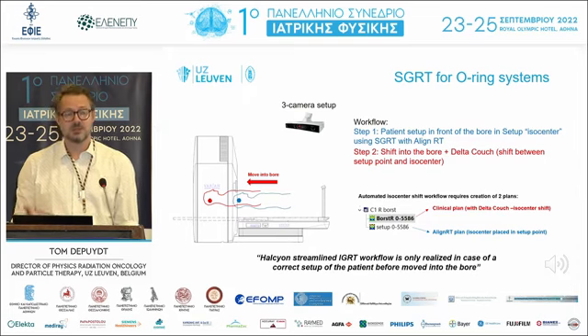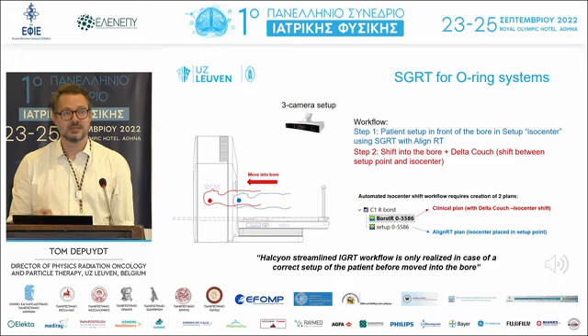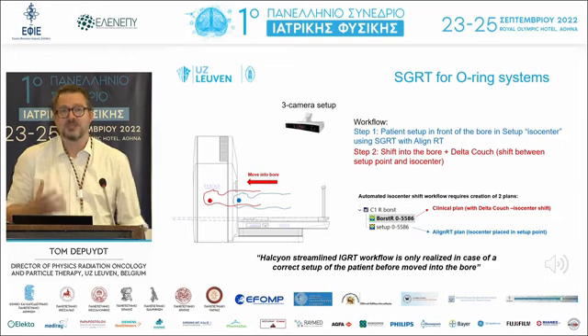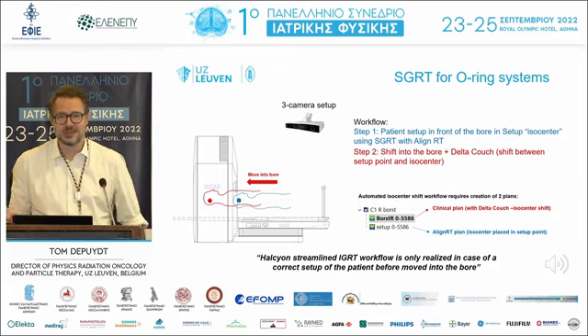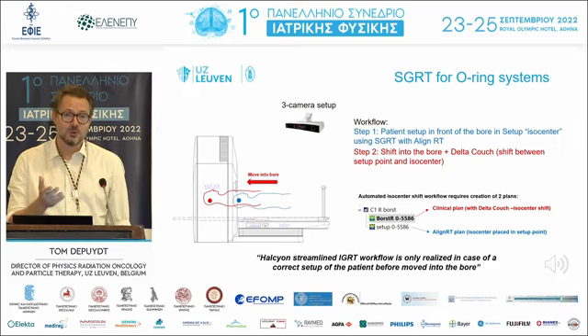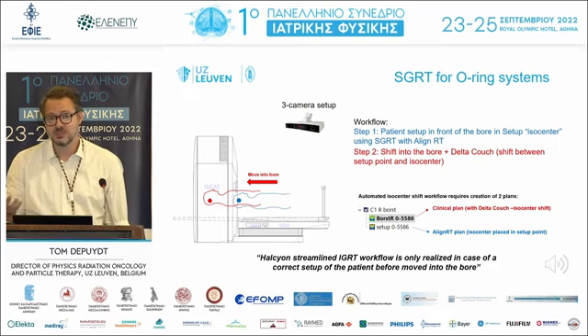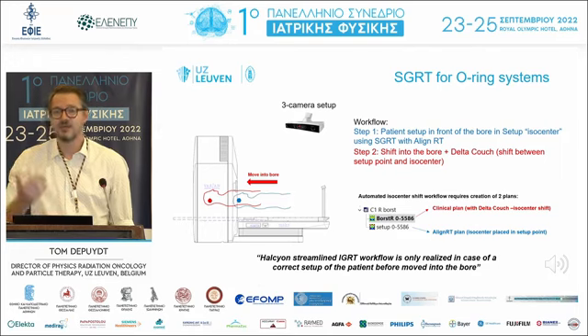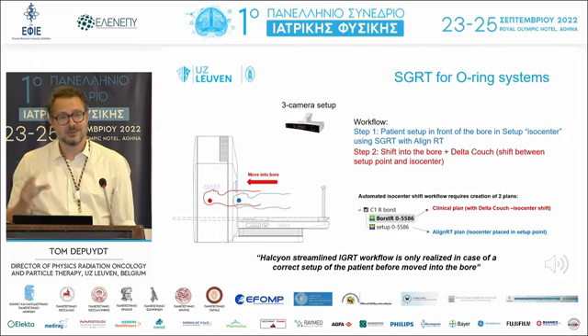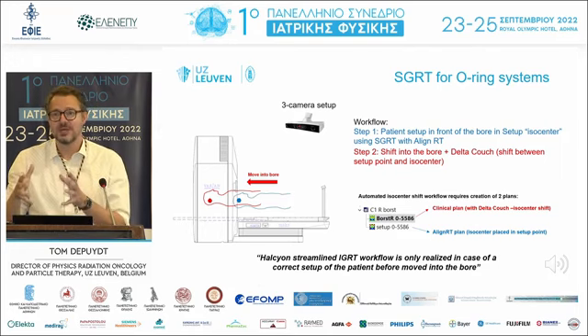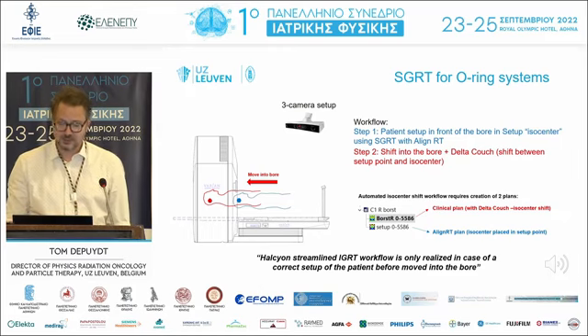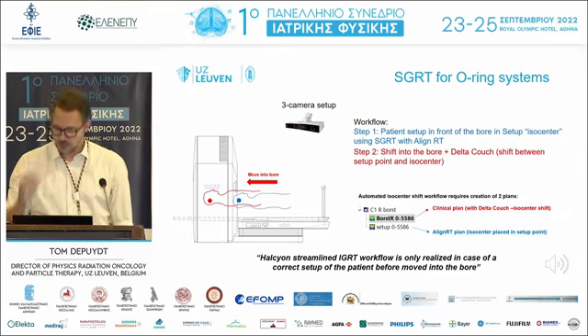So, streamlining Halcyon. Halcyon is a very fast device in the sense that it's really an efficient workflow, but one of the requirements for that is that the patient setup is correct, because otherwise you run into issues. You don't have a 6D couch, so that means you bring it into the bore, and then if, based on imaging, cone-beam CT, you see that the patient is not correctly positioned, then you have to go back in and manipulate the patient, put him in the right position, and then you lose a lot of time. So in this case, if your initial setup is correct, then you are much more efficient.